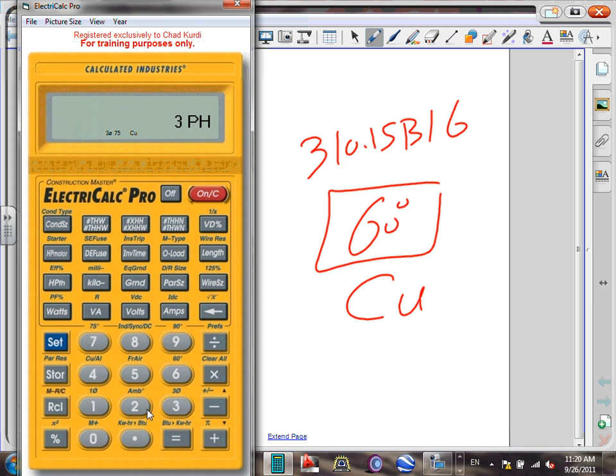Here's what I want you, I'm looking at your test, guys. I'm going to do question number 2. What is the true power of a 10 amp circuit operating at 240 with a unity power factor? Let's do this problem in the test on this calculator. So before we do anything, I want you to go erase, hit twice. So clear the memory. Hit the clear here twice. Everybody right here, hit it twice. We're clear. Since I'm not sizing anything, it doesn't matter if I'm 3-phase or single phase, but make sure you're defaulted to 3-phase 75 copper. Just leave it like this.